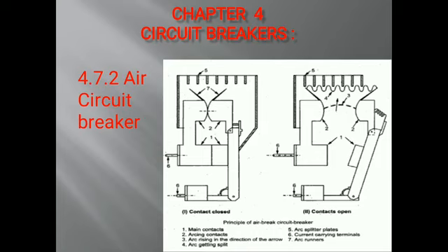Due to lengthening, cooling, and splitting effects, arc resistance increases, which will reduce the fault current and will not allow fault current to reach a high value. The current zero points in the AC wave will help the arc extinction. With increase in arc resistance, the drop across it will go on increasing.